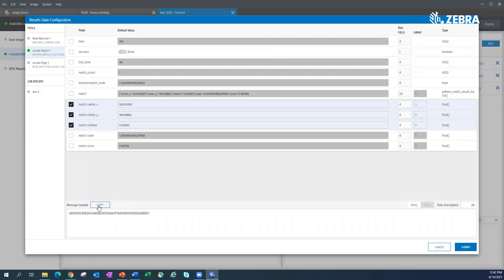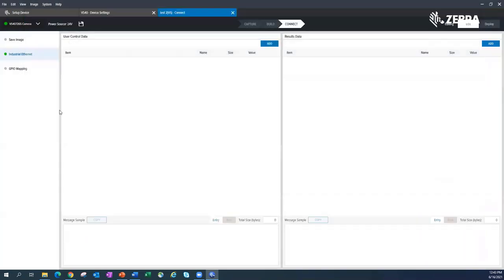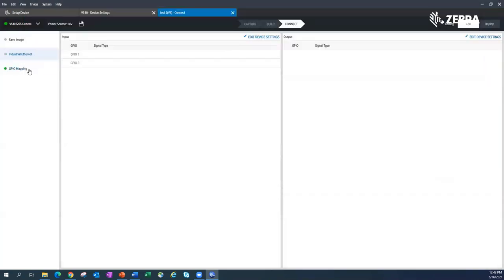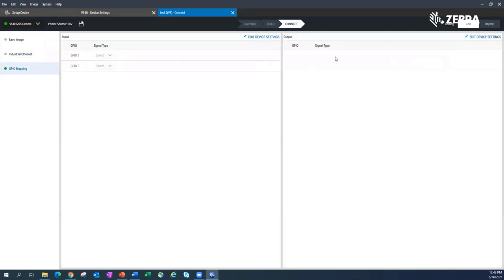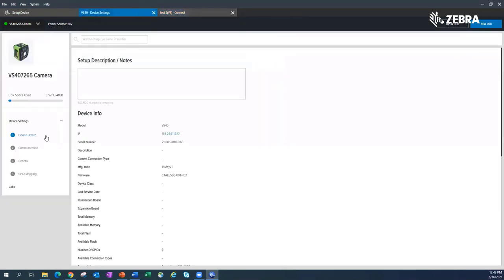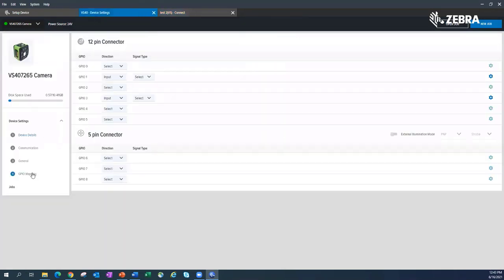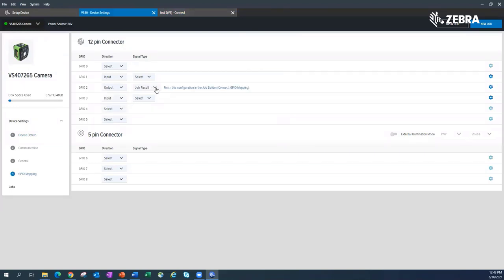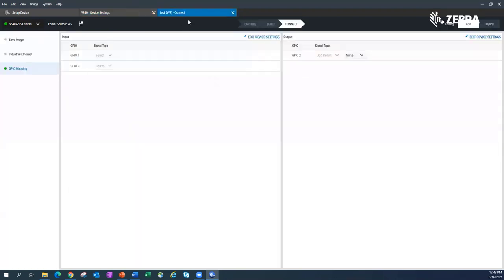I can then copy that and then paste it into my PLC program to be able to quickly sort through and parse those particular pieces of information out. So that's kind of how you send data out or get data out of the actual device itself for the Ethernet IP. We also have GPIO mapping. You remember on the first demonstration I did, you have different inputs and outputs you could set up. I don't have any currently set up for an output, but let me just do that real quick. I'll go to my GPIO and I'll say I'll make this GPIO an output.